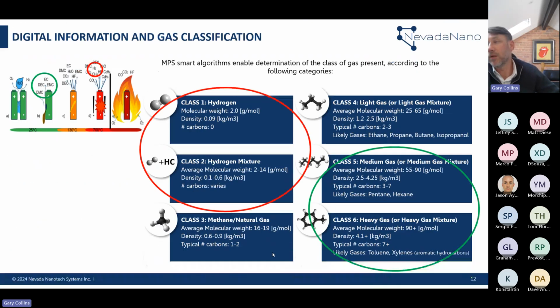If you think, how would I implement that? If you've got a digital interface and you're looking at our sensors, class 1 and class 2 will give you hydrogen across that whole spectrum. But we know from internal and external independent testing that the actual MPS will react very consistently to DMC and EMC. You'll normally see DMC in class 5 first, and then as the buildup of EMC occurs, it will transition into class 6. From a logic perspective, if you're looking for these types of gases, it's a really good way to get that early warning before a failure occurs in the batteries.